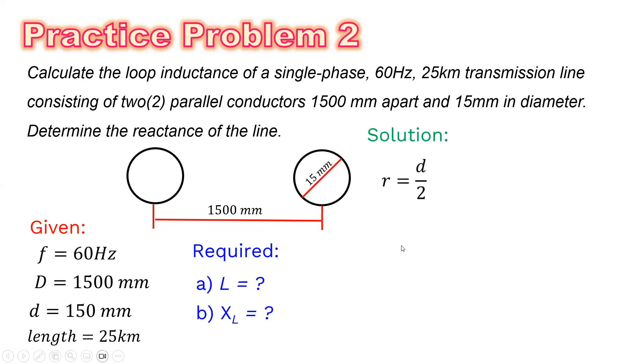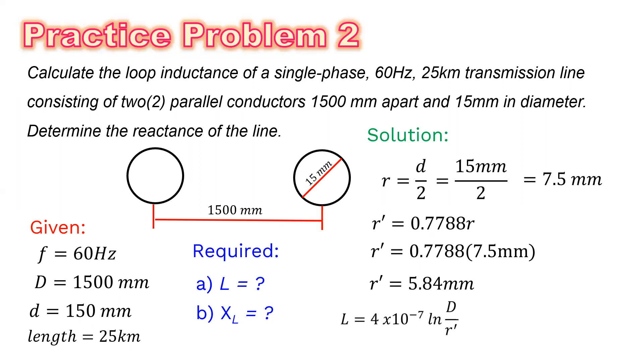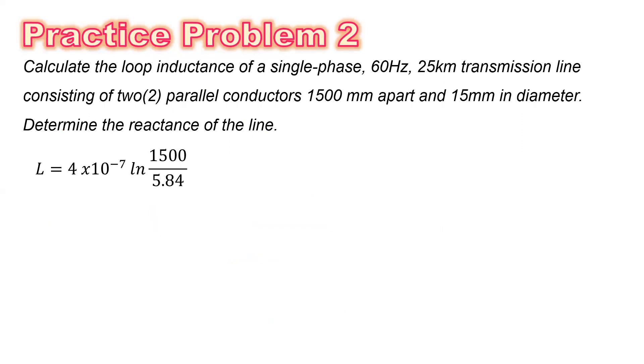First, we need to solve for the radius, which is equal to diameter divided by 2. So 15 mm divided by 2 is 7.5 mm. Now we can solve for R prime, or the GMR, which is equal to 0.7788 times R. Plugging in the computed value of radius, which is 7.5 mm, we get R prime equal to 5.84 mm. Now with the separation distance and R prime known, we can solve the inductance: 4 times 10 to the negative 7, ln of 1500 divided by 5.84, giving 2.22 times 10 to the negative 6 Henry per meter.